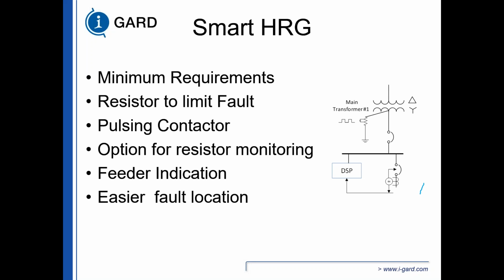More importantly, it's safer to find the fault, because right away you're driving people away from your main switchgear where you have the highest level of incident energy. You're looking downstream from the fault because you've already been given a starting place. We've eliminated all the other feeders. We're only looking at feeder 5 because that's where it's telling us we have the fault. So we start looking downstream when you turn on the pulsing. You have SIFT, or you have an adjustable timer. SIFT is Selective Instantaneous Feeder Trip.